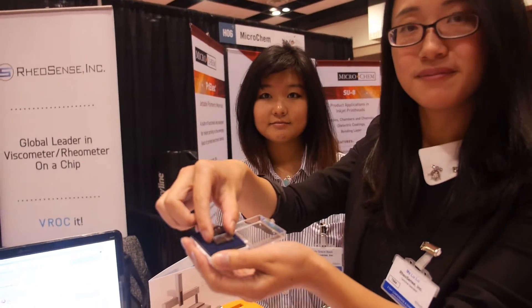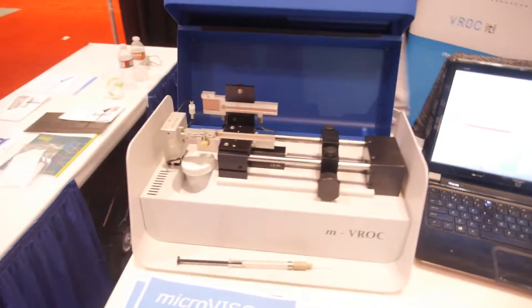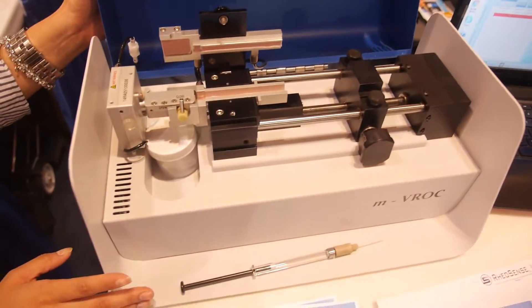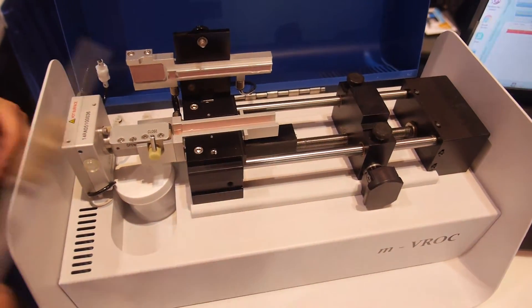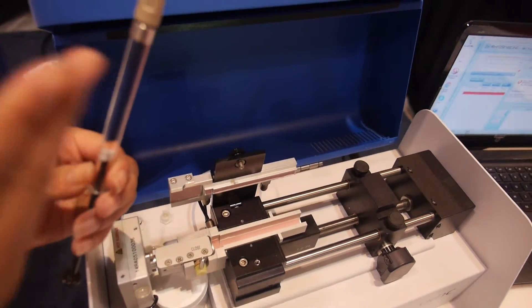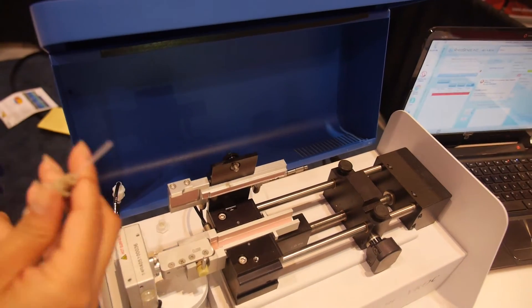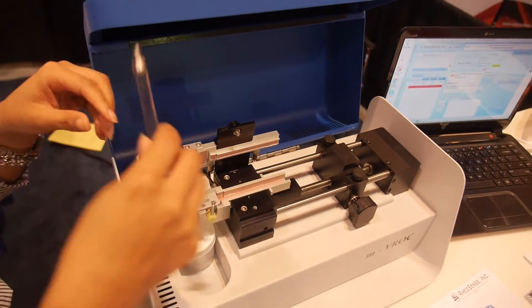So that's the chip — that's your product, and it's in this machine here. This is the m-VROC viscometer, more of a lab bench. What you do is you load your sample — we just have some water detergent solution here — and we connect it to the chip.